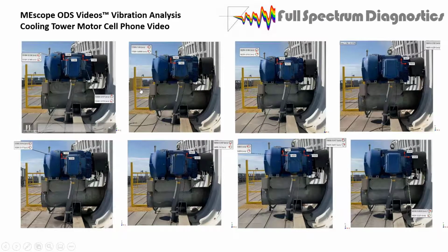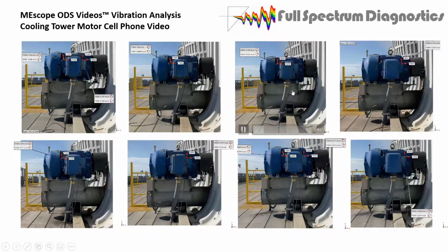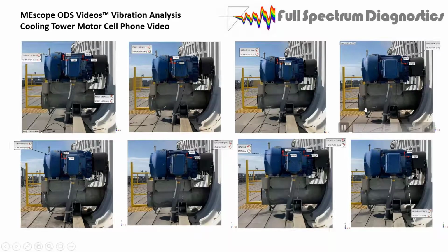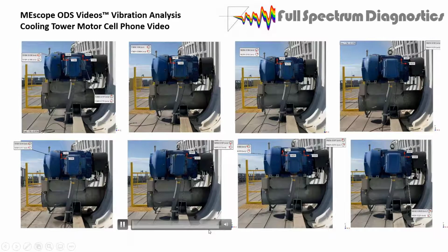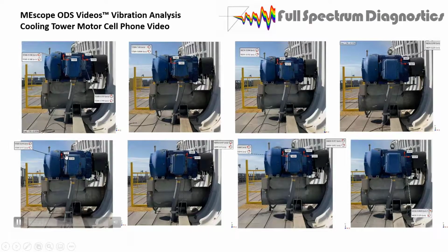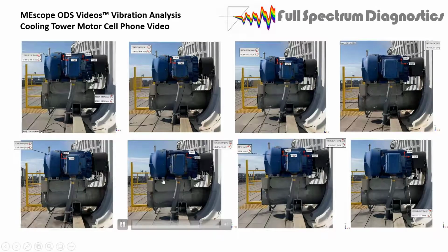So we got some vibration. This one's a little stronger. None of them are above what you'd consider an alarm level, but regardless, there's some fundamental motion here that some of them have and most of them have, but it's slightly different variations. Okay. I also took some data on here and compared it back to my accelerometer data.